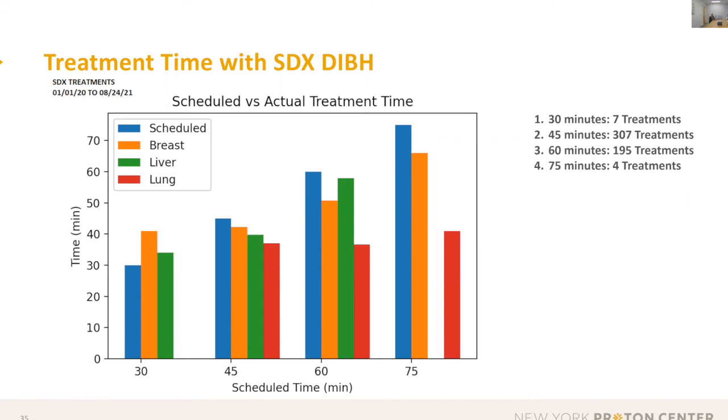That basically holds the beam and prolongs the treatment time. The other factor is we have this kind of beam model, and as I mentioned, we can adjust the dose rate. With Eclipse, we can only create the individual model to decide the minimum MU of the plan, which is the minimum MU of each layer, or decide how fast that layer can be delivered. In other words, the dose rate of the beam.